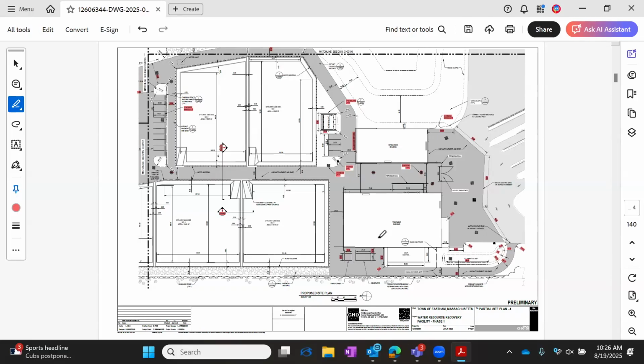That's really all we have for building fire protection. The operations building does not have a sprinkler or fire alarm system, and the salt shed doesn't either. The other trigger for the treatment building is based on the NFPA wastewater treatment evaluation, which identifies the specific hazards that exist in these different rooms based on the processes, and then the protection criteria for it. That's what triggers our fire alarm for this building as well. So in a nutshell, that's what we have.